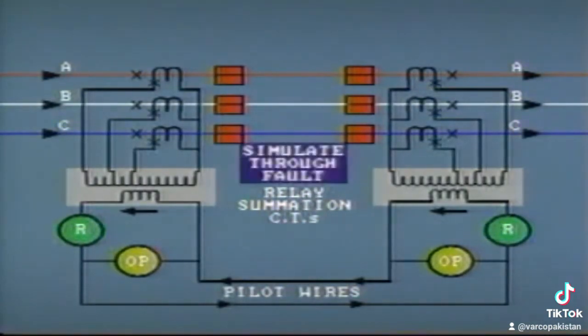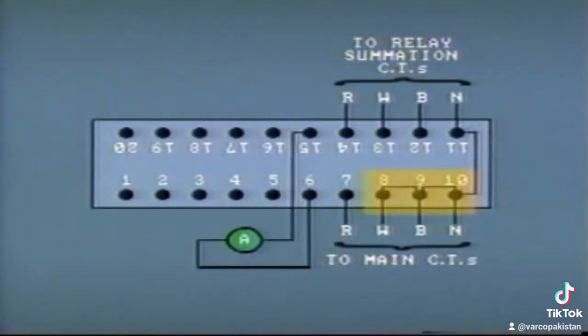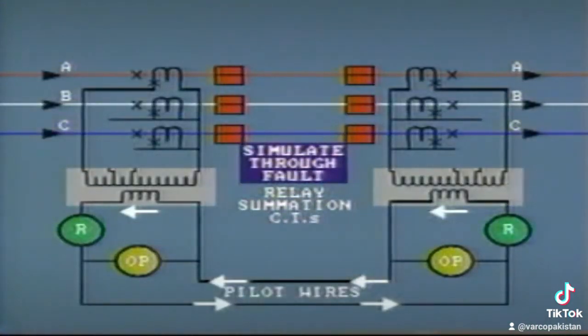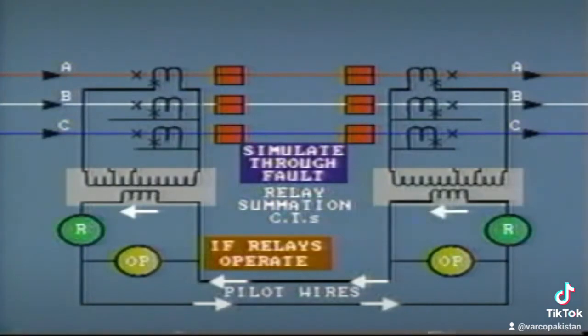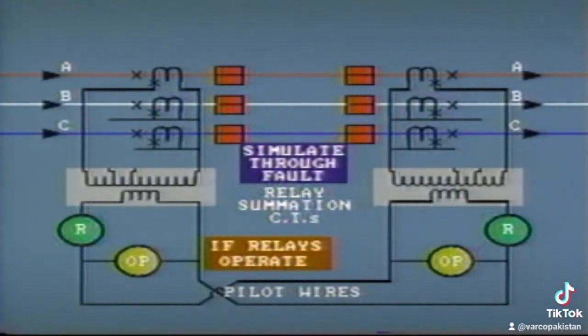We can simulate a through fault, say a ground fault on phase A, by disconnecting the CT connections to phase B and C, not forgetting to place a short across the CTs. This is usually done at the test plug board like this. With this arrangement, we should have considerable current flowing through both restraint coils and the pilot wires. Current through the operating coil should be 0 or close to 0. However, if the relays at both ends operate incorrectly, then the pilot wire connections should be reversed at one end only and the test repeated.